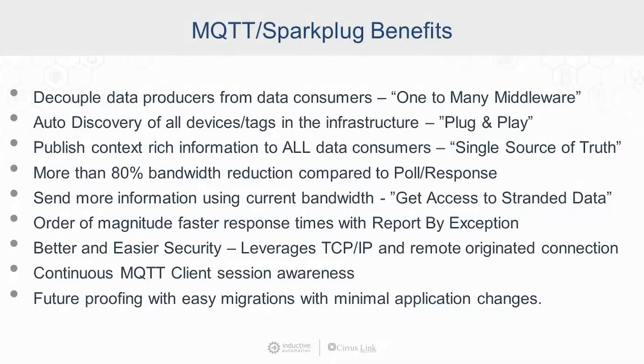Using MQTT and Sparkplug, what are the benefits? First, we've decoupled data producers from data consumers, creating a one-to-many architecture with message-oriented middleware. We have auto-discovery of all devices and tags, resulting in plug-and-play architectures. We're publishing context-rich data to all consumers — a single source of truth for one process variable tag published to one, two, ten, or a hundred data consumers. More than 80% bandwidth reduction compared to poll-response means we can send more information using currently available bandwidth, giving access to 80–90% more data that used to be stranded. We also get an order of magnitude faster response times with report-by-exception.